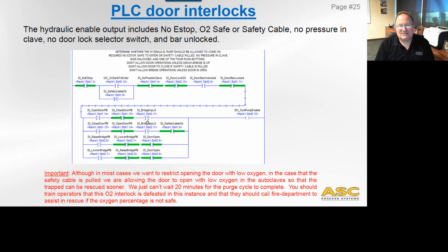So what do we have here? Let's start with door interlocks. Normally there's a hydraulic enable output of the PLC, and that is going to be fed from the PLC logic. And as you see here, we have no e-stop, O2 safe to enter, no pressure in the autoclave, door lock limit switch is not in the lock position, the door bar is unlocked and it's not locked, and then we can operate the hydraulics based on our push buttons.